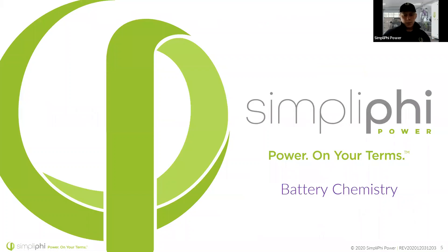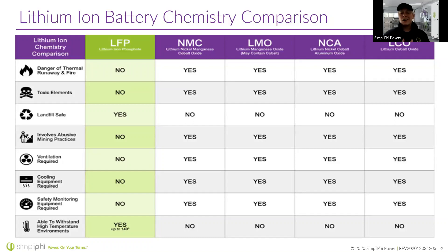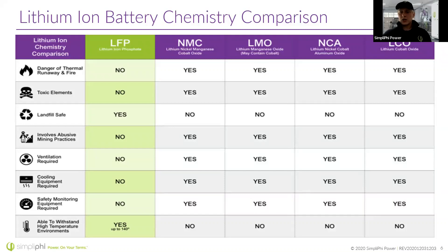Talking about battery chemistry specifically — there are many options, and lithium is not all the same. Lithium ion can mean a whole number of different things. NMC batteries contain cobalt, which is extremely energy dense but also thermally unstable, making the battery a bit unsafe — it can catch fire if it goes into thermal runaway. Lithium iron phosphate, on the other hand, is really not able to release heat quickly enough to start a fire because it doesn't contain that energy-dense cobalt. Yes, it's a little less energy dense, but it's a whole lot safer.